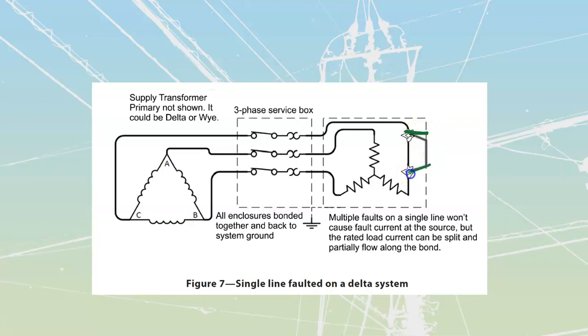If I make two connections, as shown here, I could split a tiny bit of current coming in from my main line — a small split going like that and like that — but ultimately all of that current hogs back together and goes back through the load. So we won't see any increase in current that would trip it out. As long as any faults are on the exact same line, nothing happens for actual fault current.